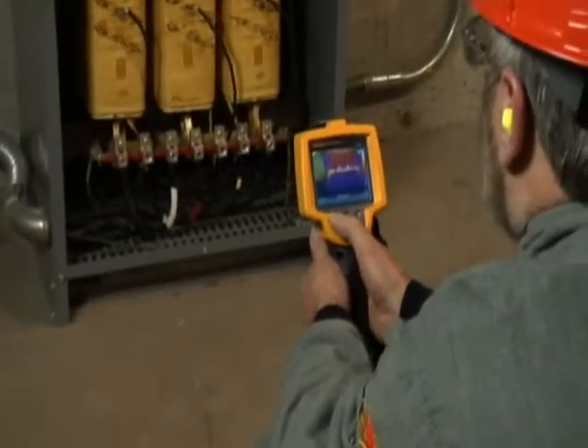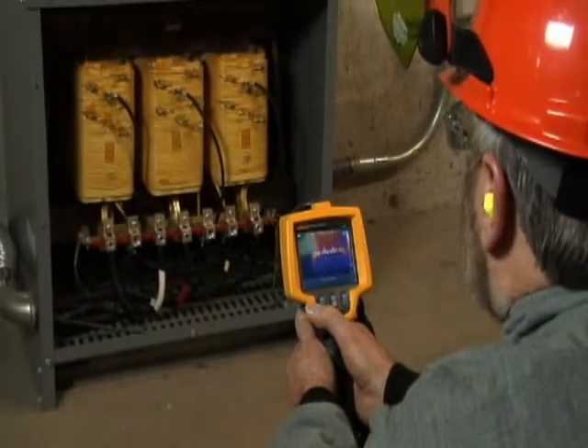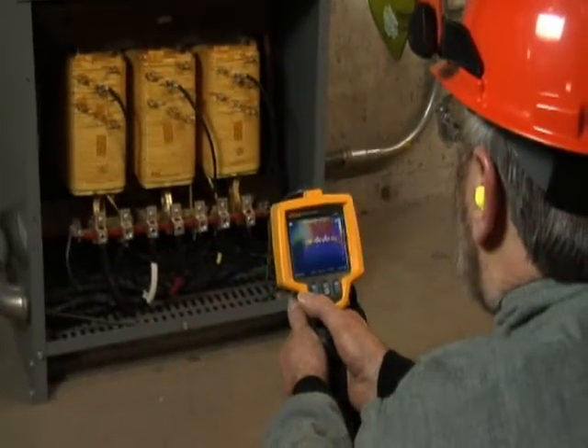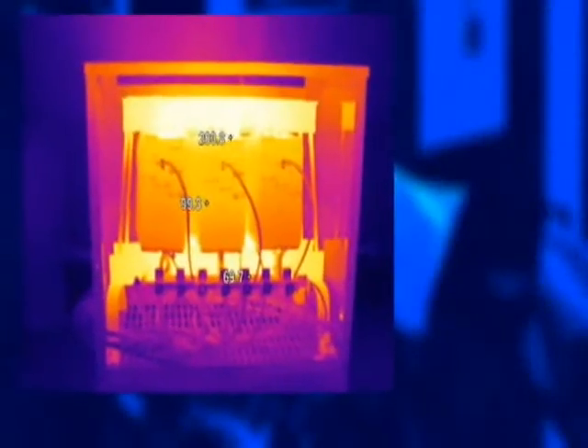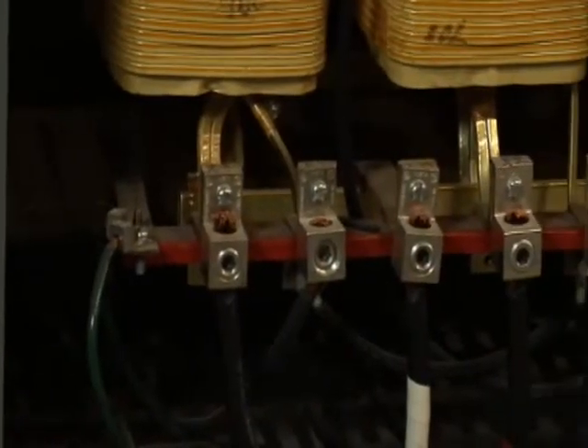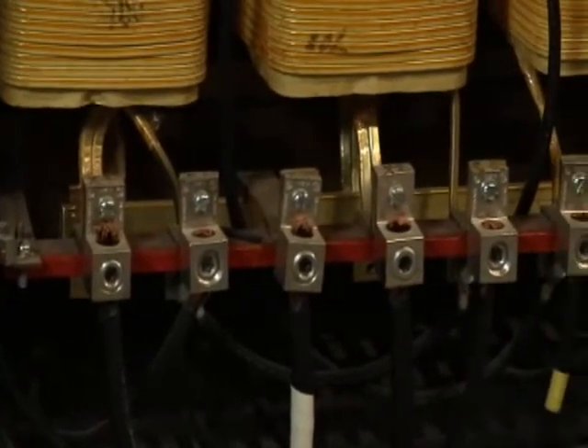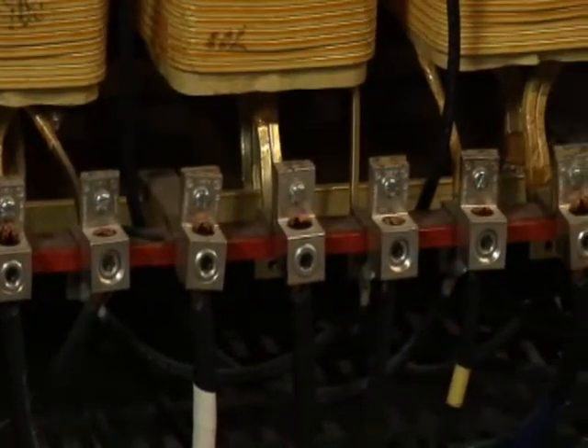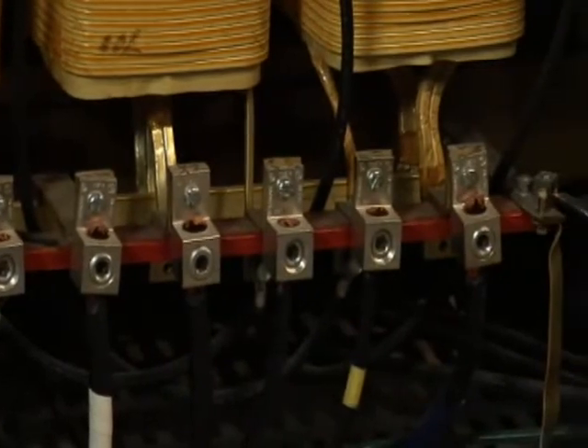If the temperatures you read throughout the transformer are substantially higher than expected, and the unit isn't in direct sun, then you've got a problem with overloading and cooling. Another thing to look for in a thermal scan is loose connections. Long-term vibration can loosen connections, and this can cause both overheating and sometimes excessive buzzing.